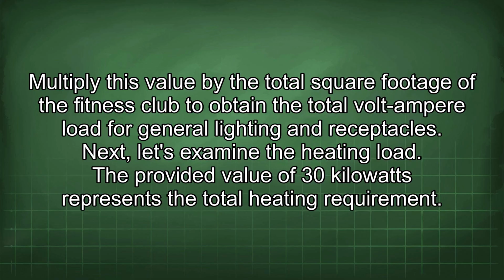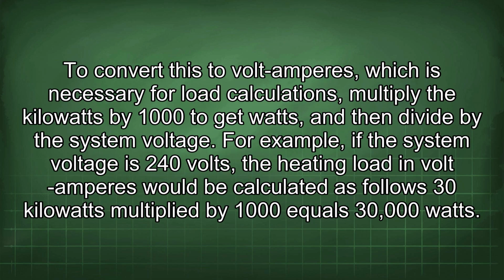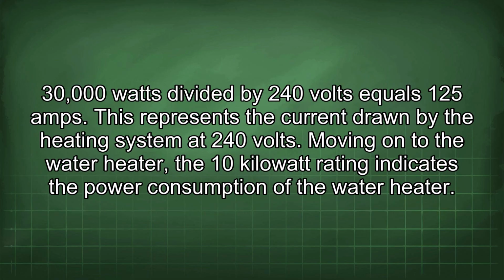The provided value of 30 kilowatts represents the total heating requirement. To convert this to volt-amperes, which is necessary for load calculations, multiply the kilowatts by 1000 to get watts, and then divide by the system voltage. For example, if the system voltage is 240 volts, the heating load would be calculated as follows: 30 kilowatts multiplied by 1000 equals 30,000 watts. 30,000 watts divided by 240 volts equals 125 amps. This represents the current drawn by the heating system at 240 volts.